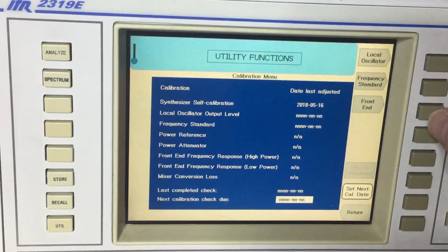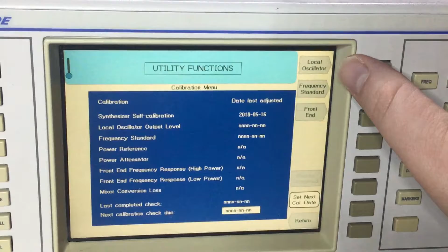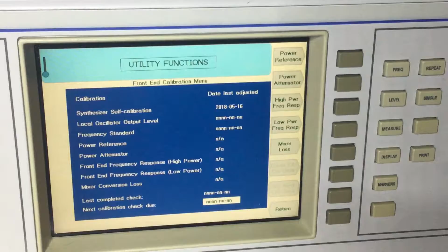Serial number unlock as well, there's all that feature on it. And now we've got under calibration these options here, you see. Local oscillator, frequency standard, and then we've got the front end. And I went into the front end, and this is where you can set up the RF levels that are coming in, because as you can see there, we've got a power reference, which sets up obviously the reference power attenuator, and then we've got the high power frequency response, low power frequency response, and mixer loss. So you can sort of set things up in there.